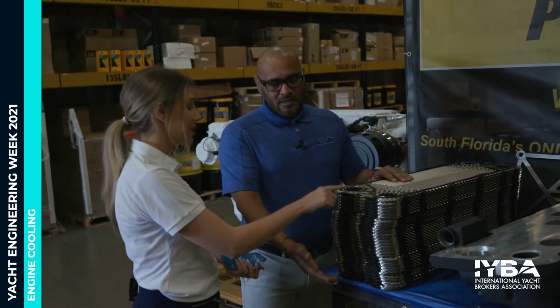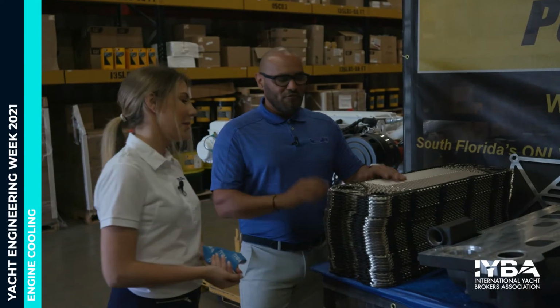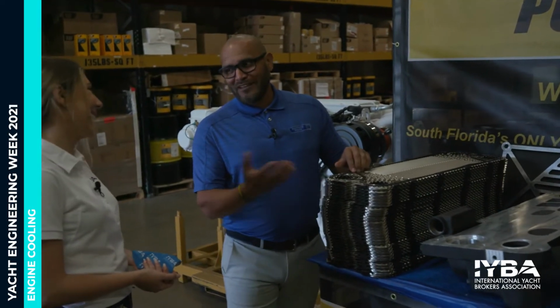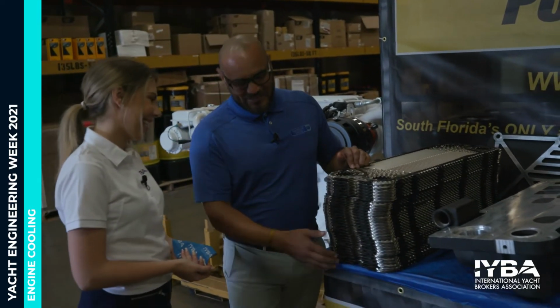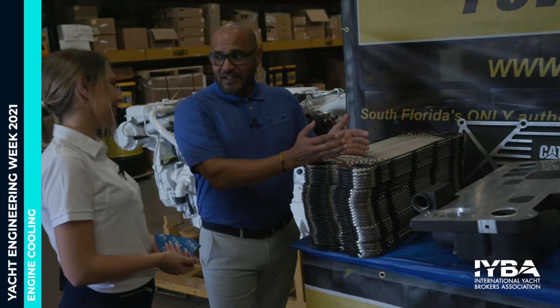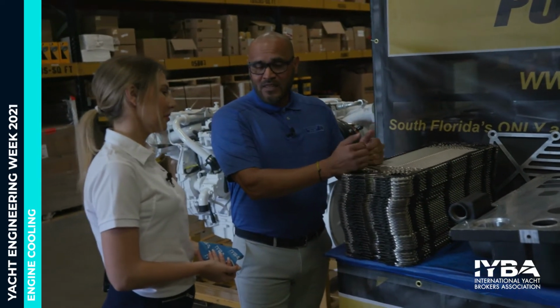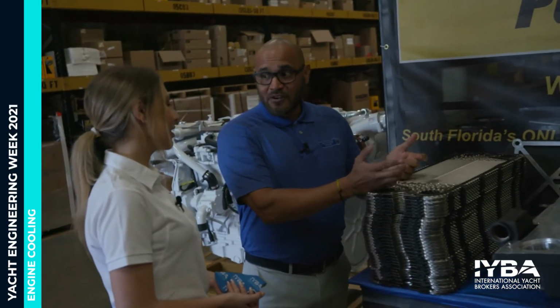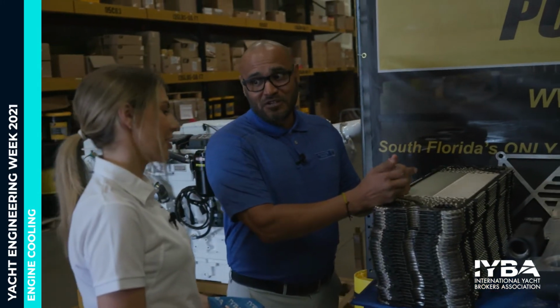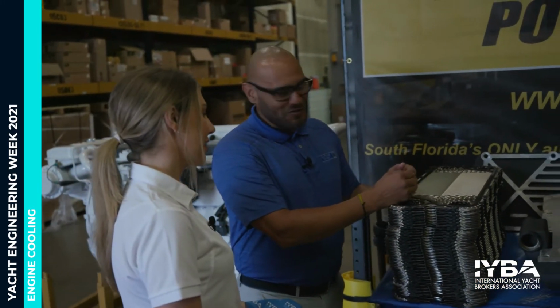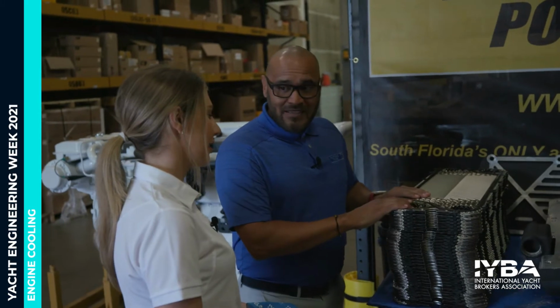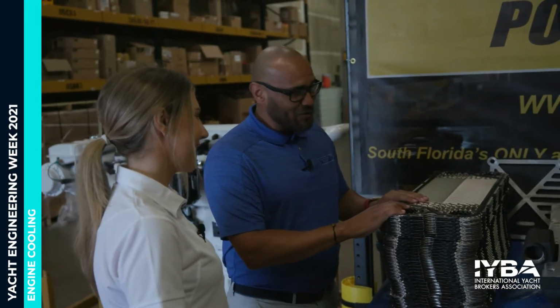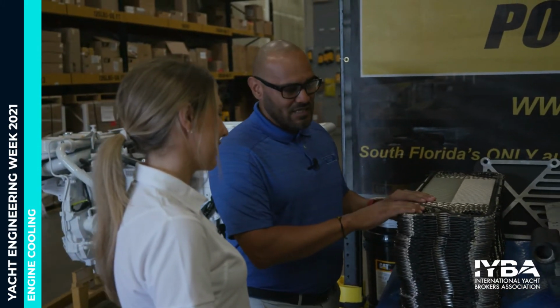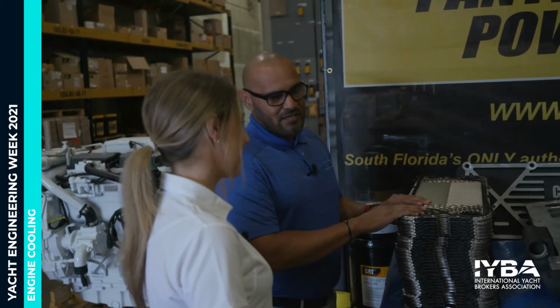So then you will need to replace all of them. Because for you to go through and measure every single one to find the 3 that are bad isn't worth it — you might find the 3 or 6 or 10 that are bad, but shortly after, another 3 or 6 or 10 will go bad too, and then you're going to have a leak, and that's not good customer service. So we want to maintain maintenance, stay on your intervals, stay on your schedule, because that's what keeps your maintenance costs down.